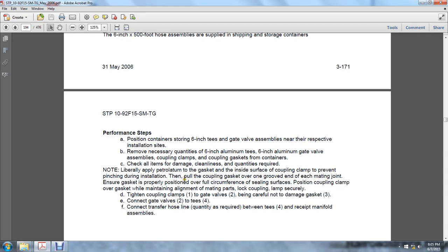Liberally apply petrolatum to the gasket and the inside surface of the coupling clamp to prevent pinching during the installation. Pull the coupling gasket over one of the grooved ends of each mating joint. Ensure the gasket is properly positioned over the circumference of the seal surface. Position the coupling clamp over the gasket while maintaining alignment of the mating parts. Lock the clamp and secure.